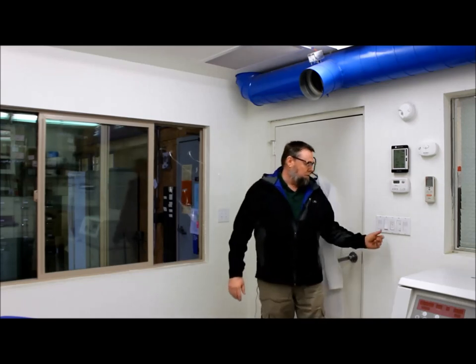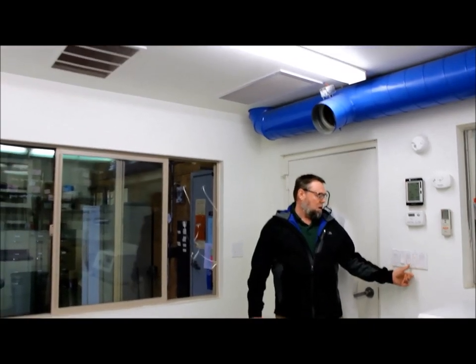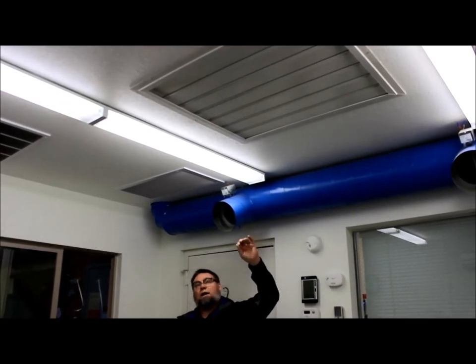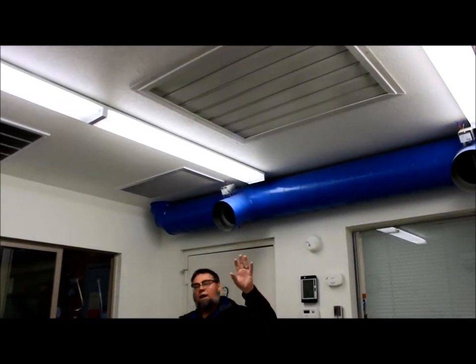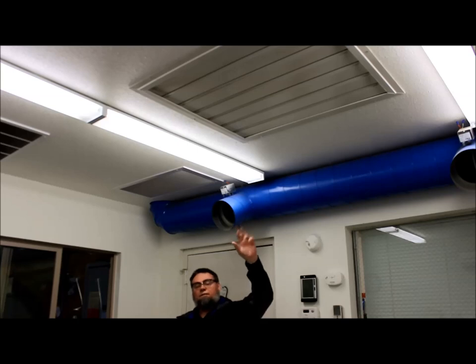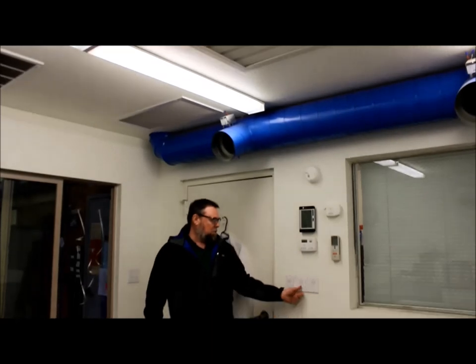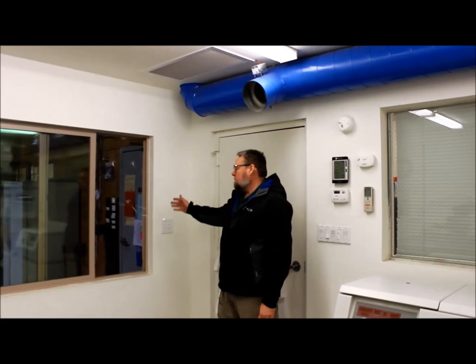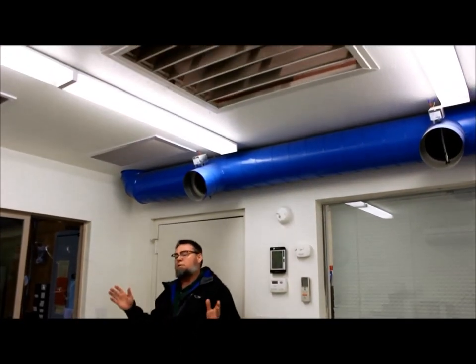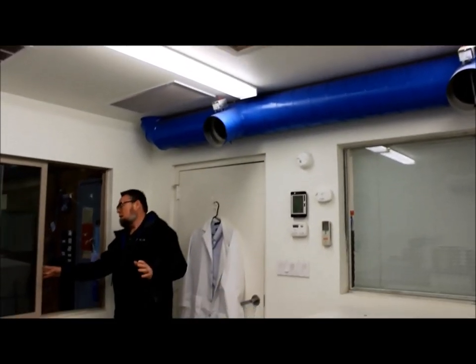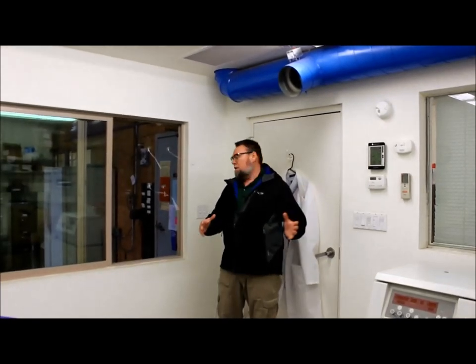From that fan, we're going to move over to our 30 inch whole house fan, which is a standard 30 inch type whole house fan. It takes a big space, moves a whole lot of air. These fans are around 7000 CFM when they're fully on. At half speed, about 4000 CFM. We're going to put this one on low. You'll notice the streamers are moving quite a bit more. Actually, I think this is about 5000 cubic feet of air a minute. I have to open the window more to allow the air to move in better.